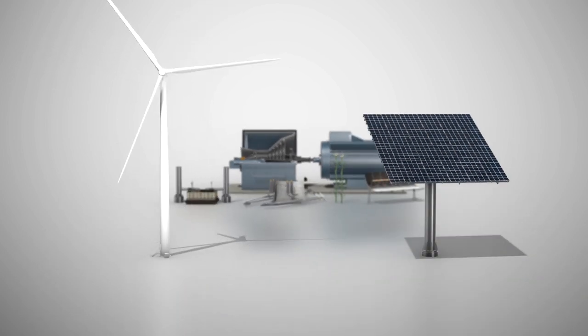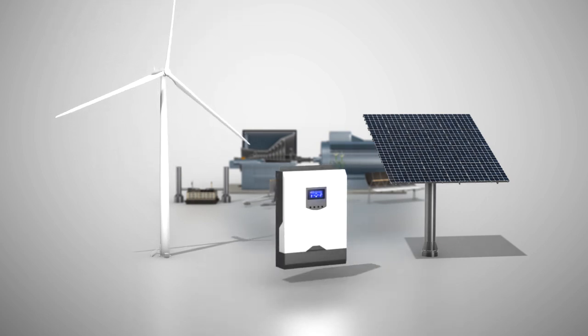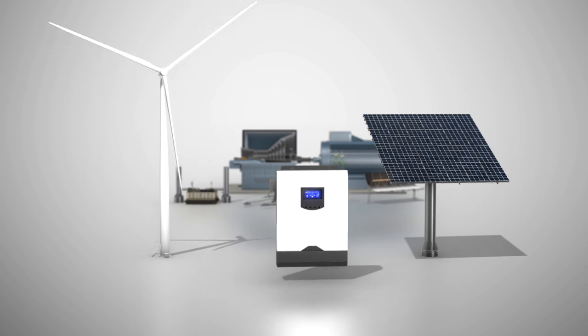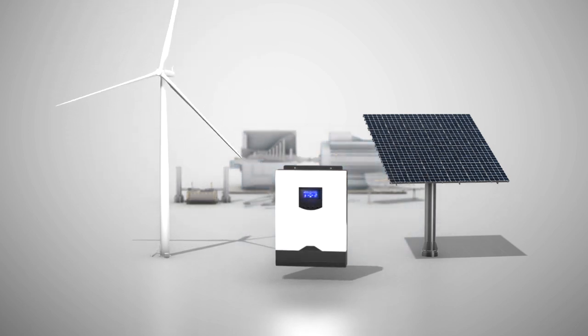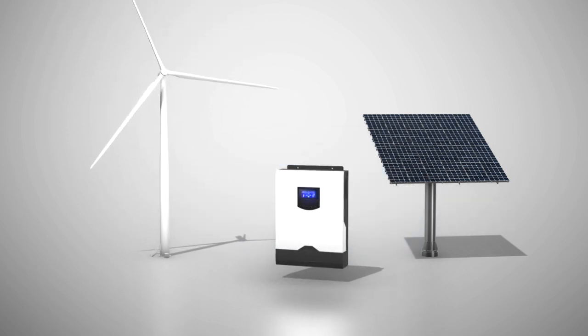But variable generation renewables like wind and solar PV don't use traditional generators. Instead, they use inverters, which have electronic controls that do not provide inherent inertial response. And when we add inverter-based renewables and start turning traditional generators off, we have less inertia on the system. Does this mean doom for the grid? No.